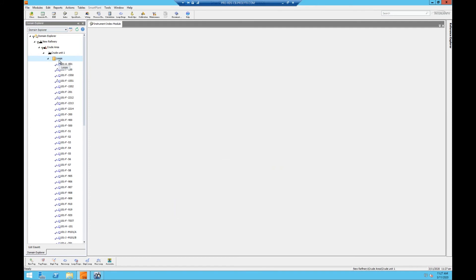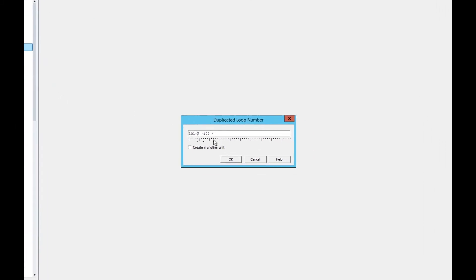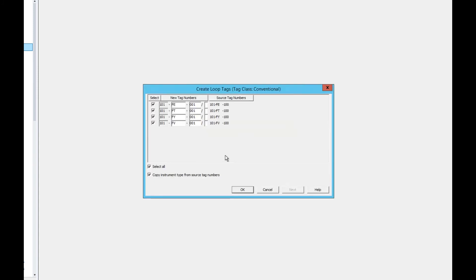Now that our preferences are set, we can duplicate our loop. To duplicate a loop and instrument, we'll right-click the loop and click Duplicate. It will ask us to name our new loop, which we'll name F001, and click OK. This will open the Create Loop Tags window where we can choose which tags we want to duplicate from the original loop. We can select and unselect the tags to duplicate. The Copy Instrument Type from Source Tag Numbers box is very important — checking it enables you to keep the instrument type of the new tags the same as the source tag numbers.